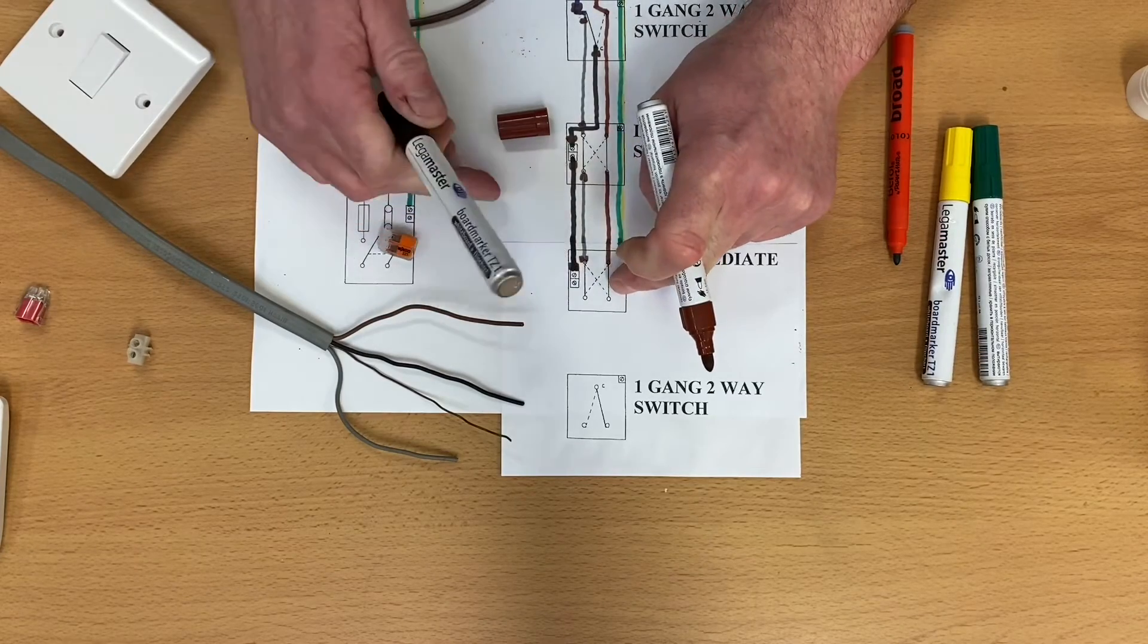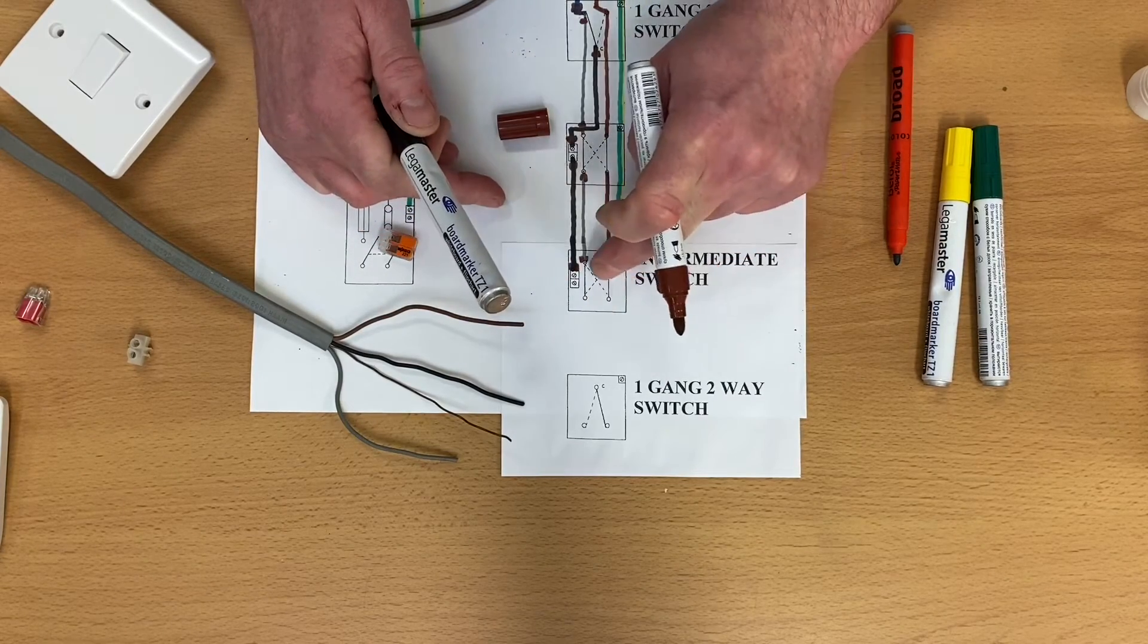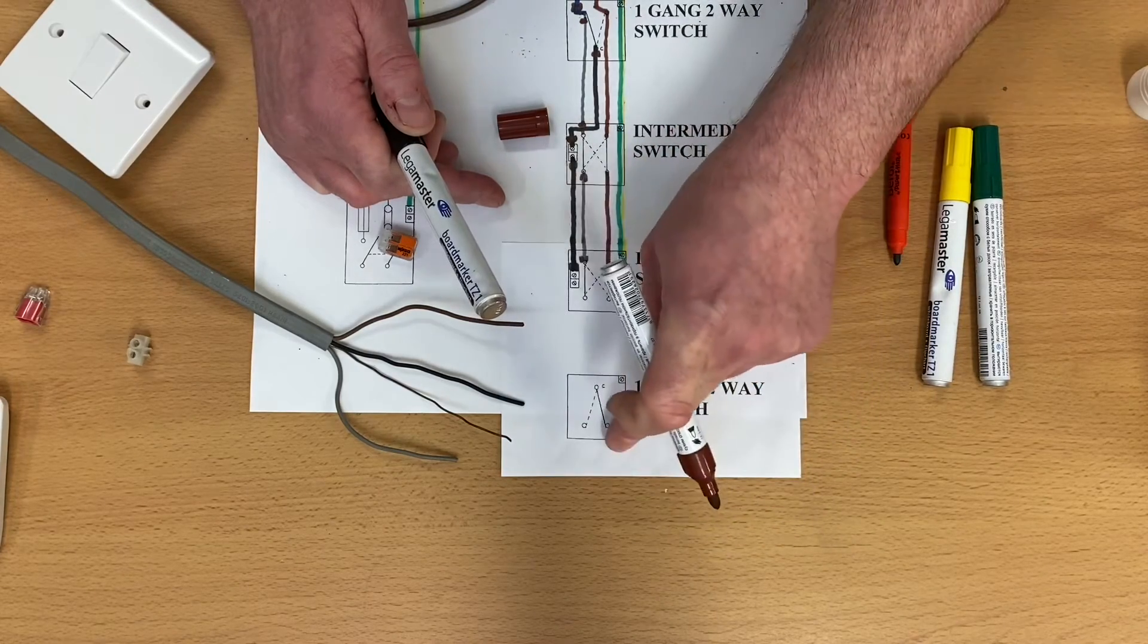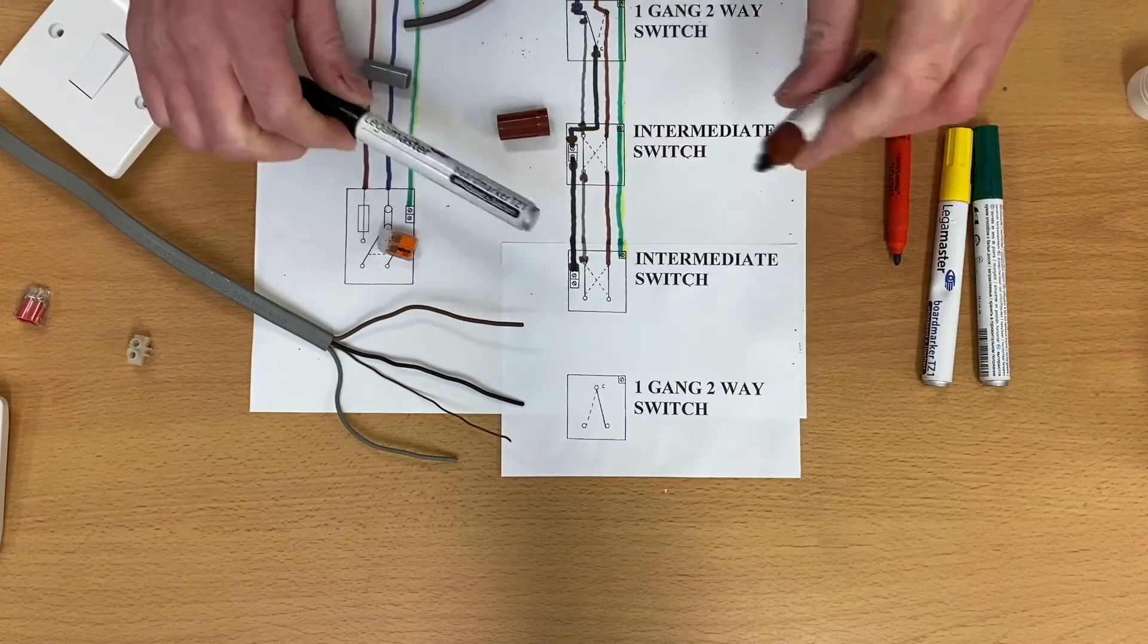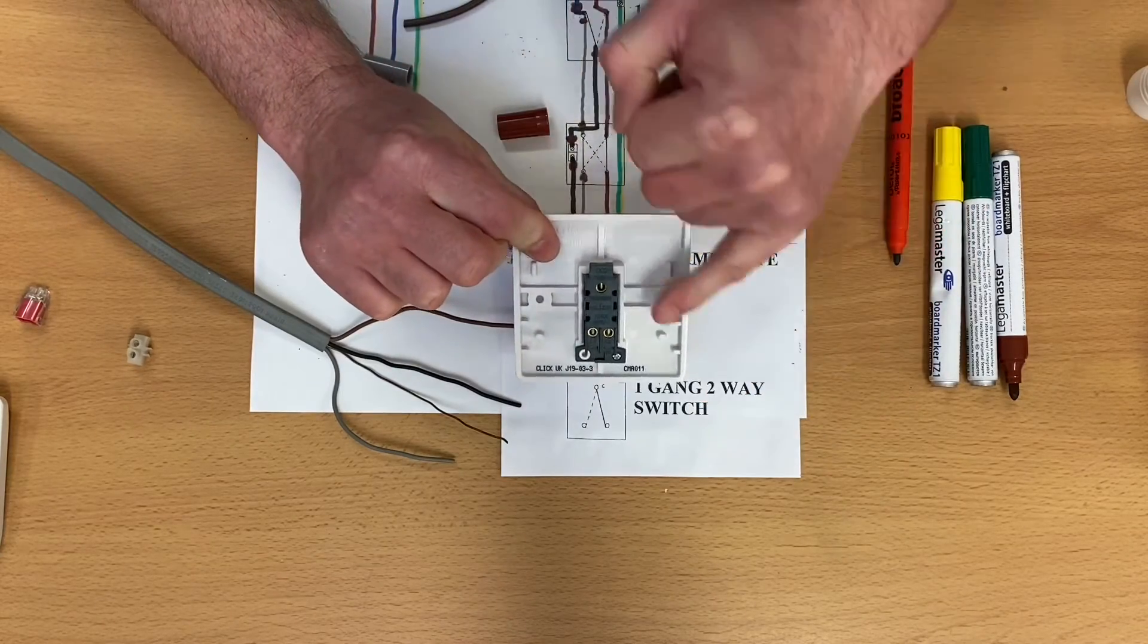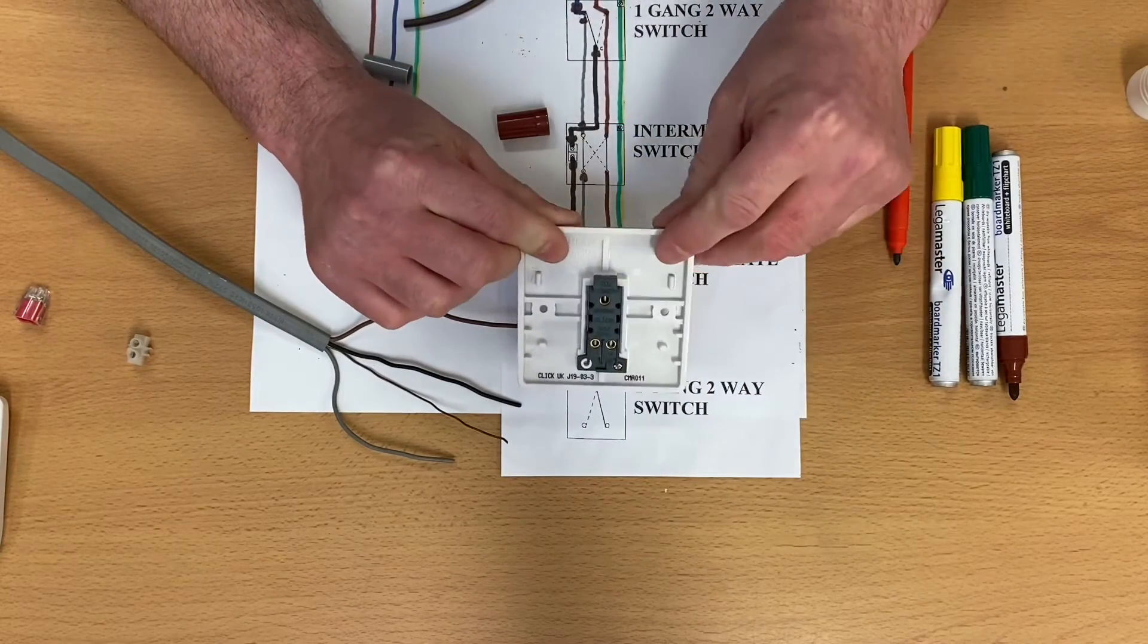So that was the three-core cable that we had originally that was in the switch under here, which was two-way, which is now an intermediate switch. We now wire into our fourth switch, and that's where we're ending it. So we know the last switch and first switch in two-way and intermediate needs to be a two-way switch. So we've got a two-way switch down here, like so. So we've got our two-way switch, common L1 and L2, or variants on that.